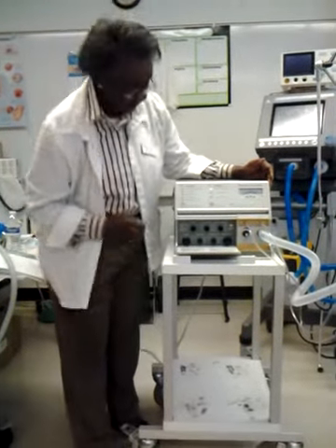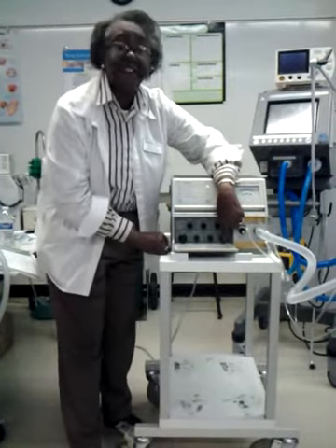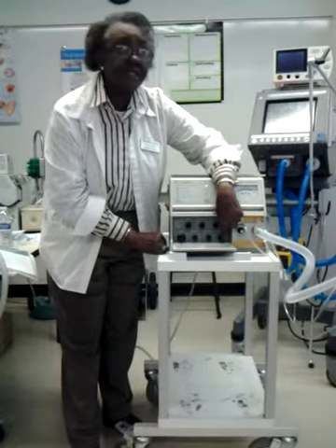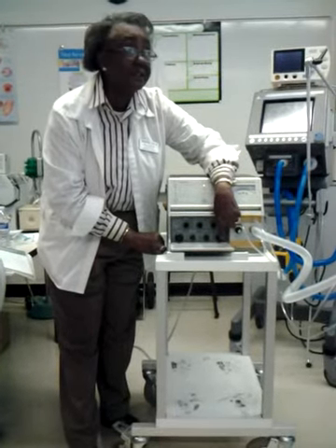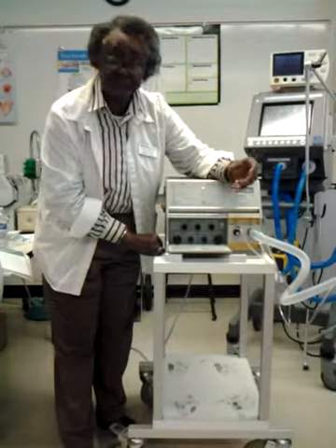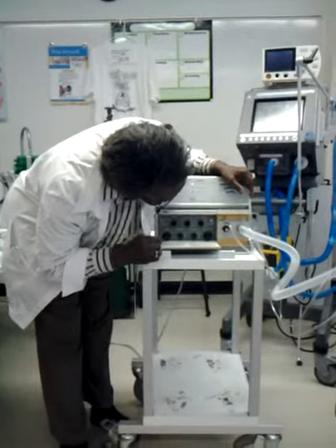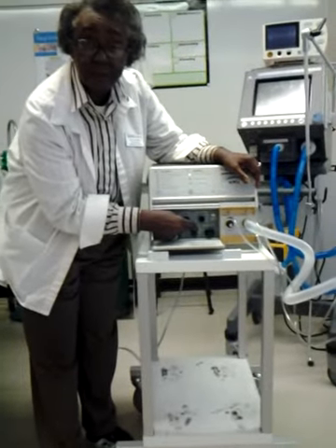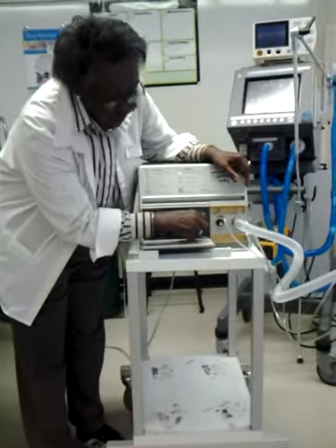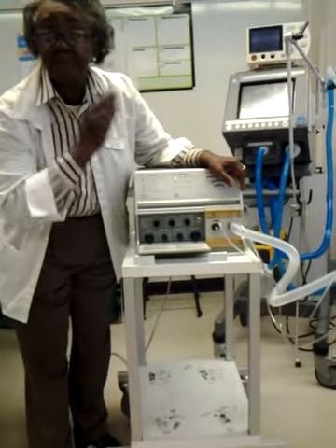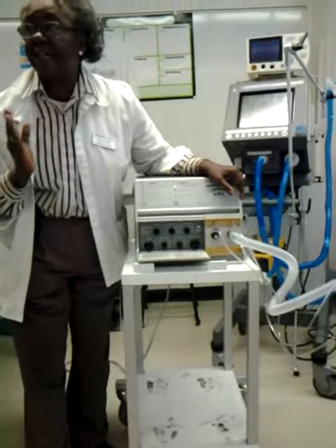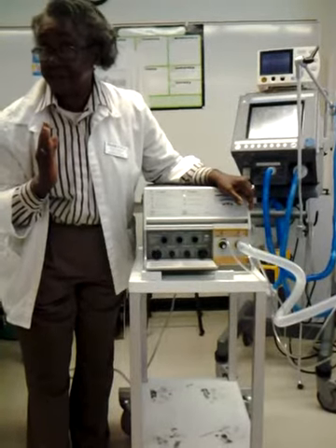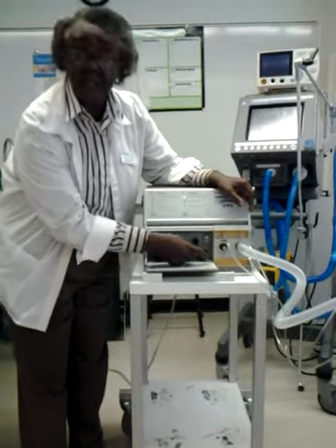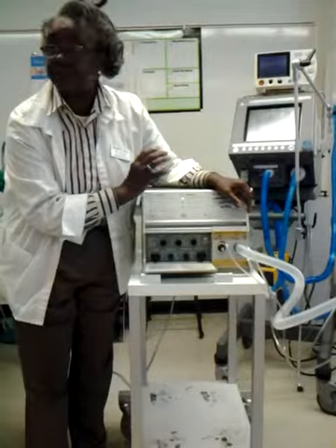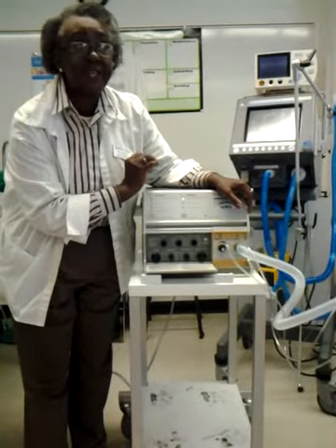Right. And then you have, this is actually your sensitivity button, but as you can see, there are no numbers on there, so you just have to kind of play with it to see how your patient is being ventilated. If you can tell by looking at it, on the green side here it's negative pressure, so it's pressure ventilation. On the other side, the blue side, it says positive pressure, but that actually takes it into a flow sensitivity. And if you go too high on that positive side, it will autocycle, so you really have to be careful when you're setting that and set it precisely.